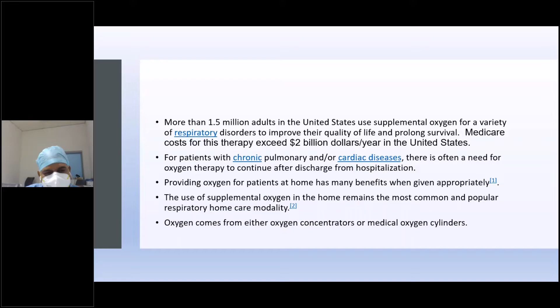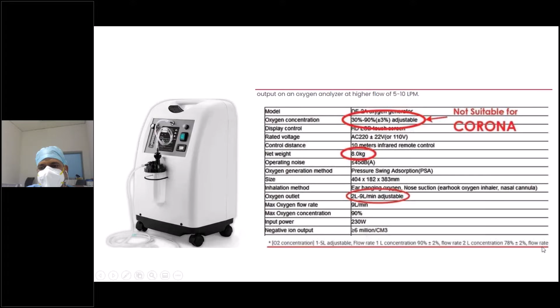So this is the typical oxygen concentrator, which may be 1 to 5 liter or 5 to 10 liter depending on the manufacturer. If you see the oxygen range, it might show 90% plus or minus 3, but if you go into the detail, it will say that at 1 liter it's giving 90%, and at 5 or 10 liters it's giving just 30%. Most of the portable oxygen concentrators meant for home use are not good enough for the COVID period, but still people are buying and using them. If you see the concentration here, it's pretty low.